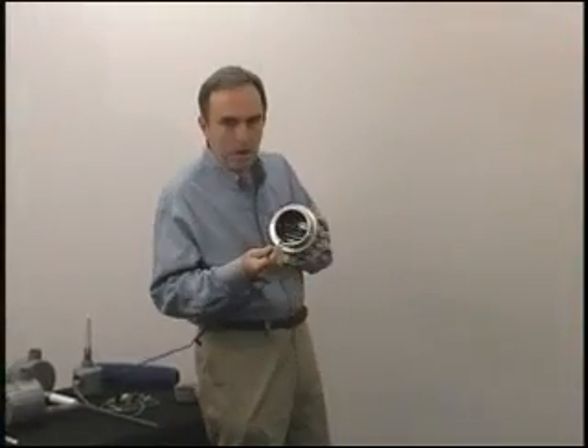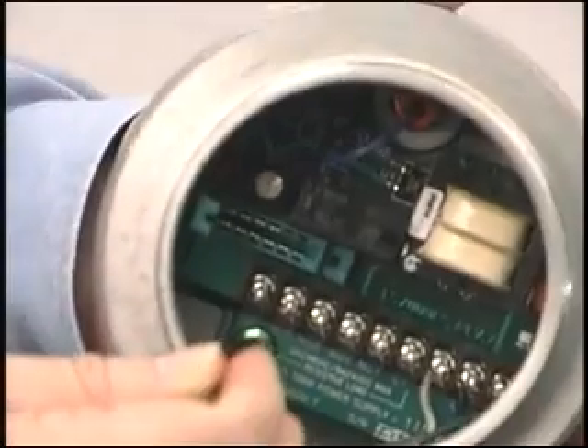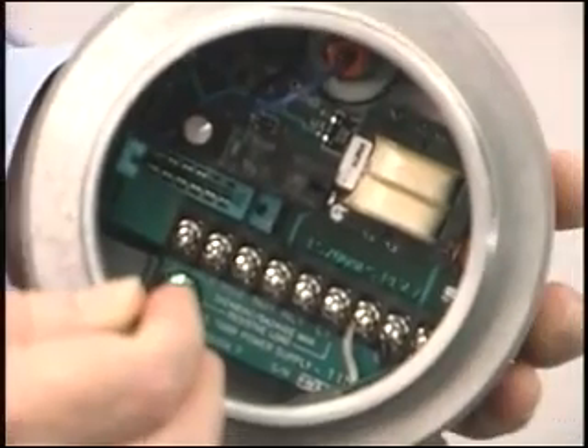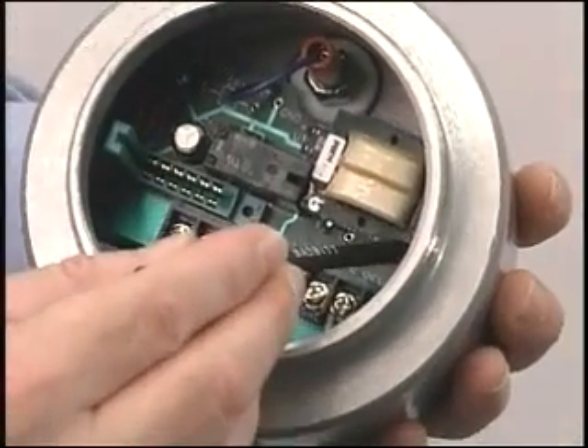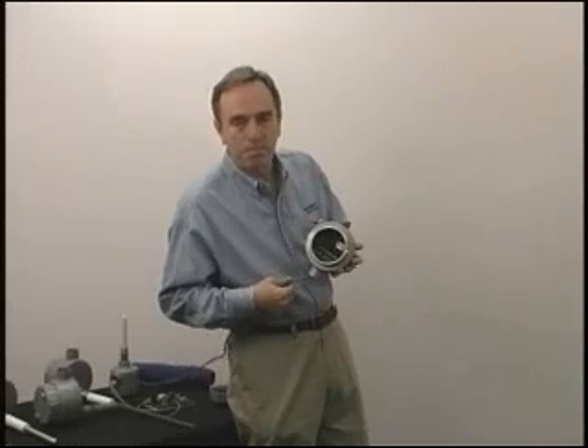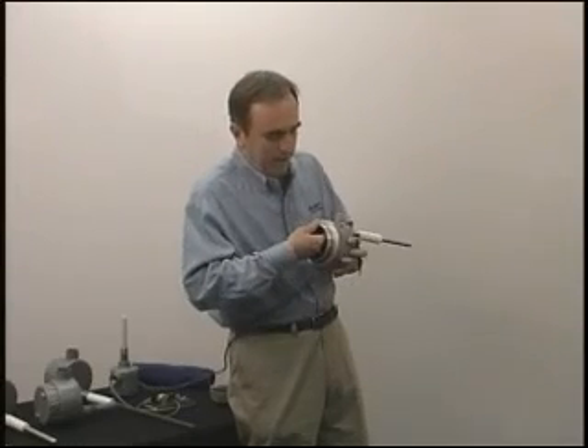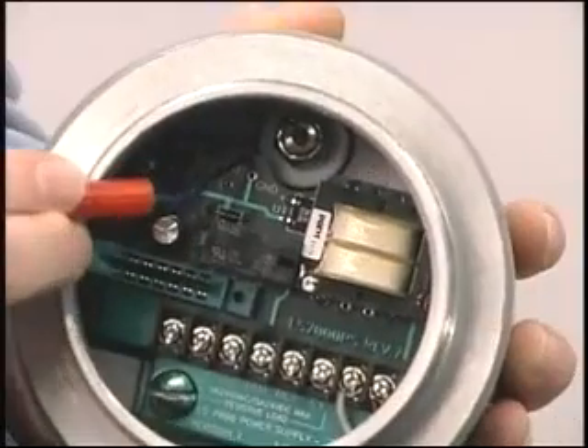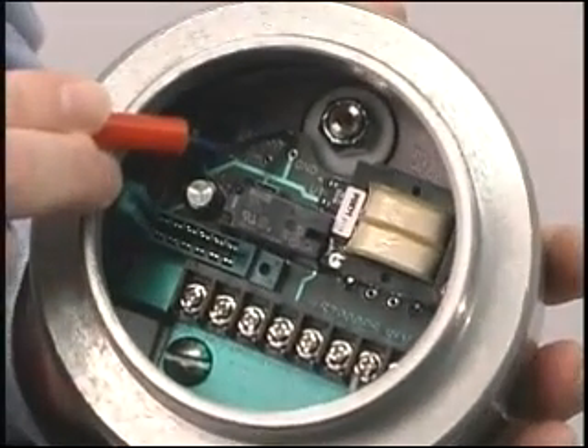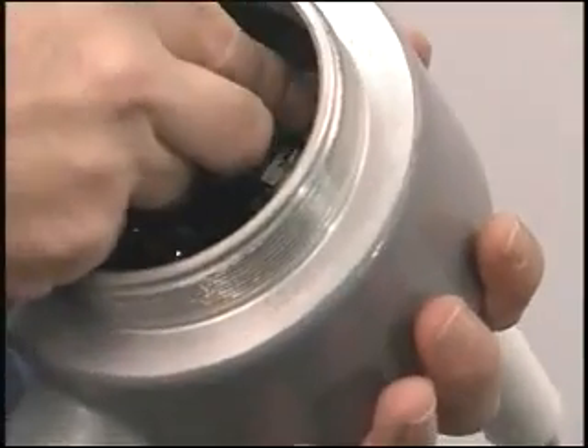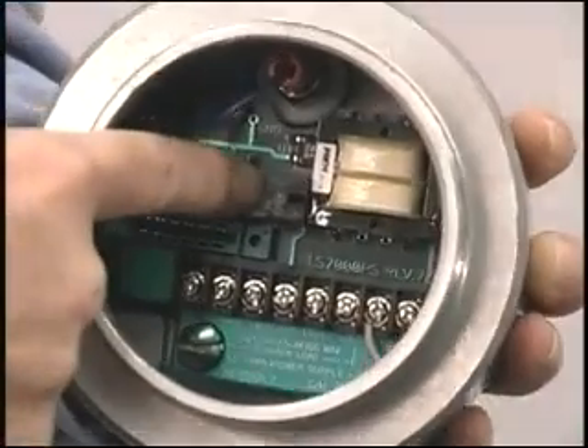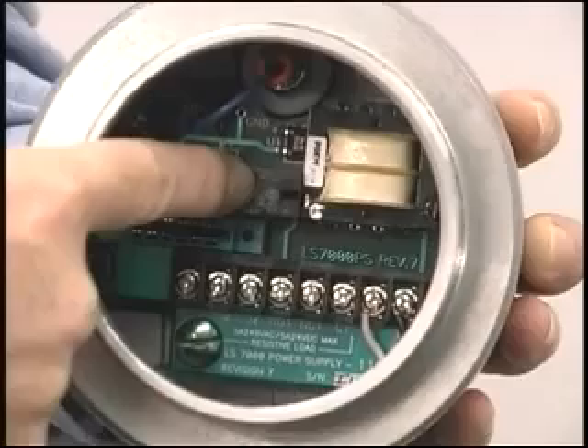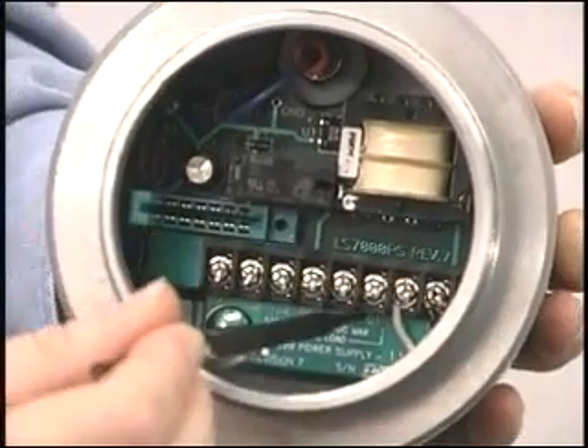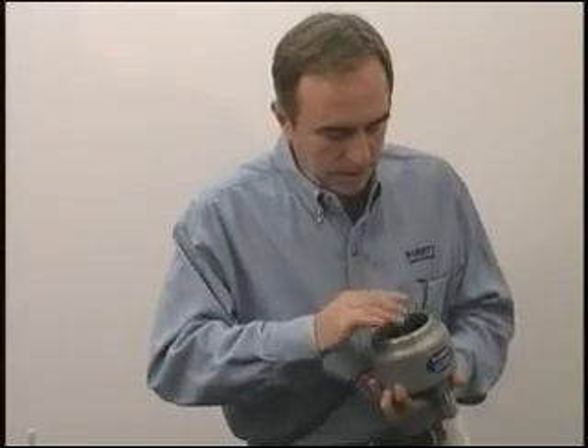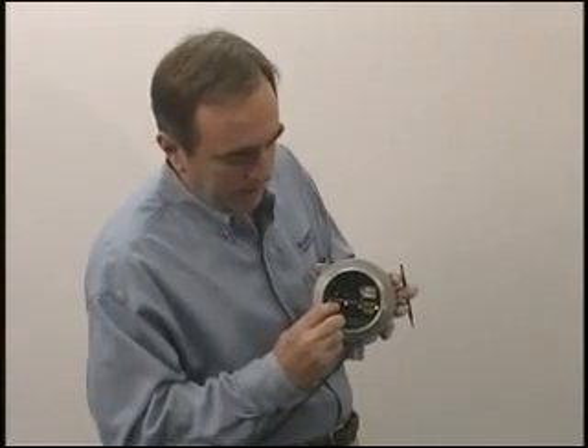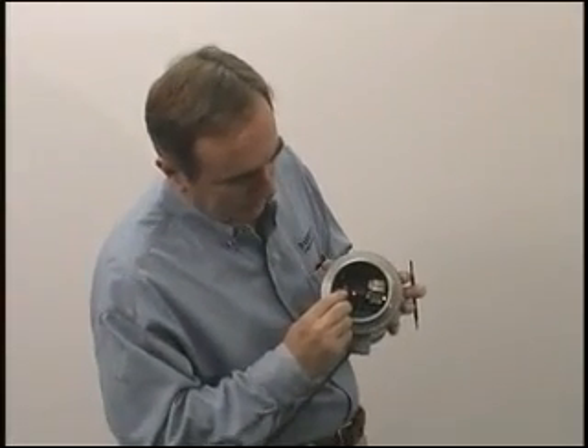The bottom card is what we call the power supply board. There's a large green grounding screw here that holds the electronics in place. There's a built-in fuse and surge arrestor that protect it from bad supply voltages. And that solid stainless steel rod just has a hole drilled in the end. The banana plug loads the signal onto the probe. So very quick change out in the field. The relay output is 5 amp double pole double throw. Bring your power in over here. Your relay contacts out here. Plug in the electronics. There's that test switch I was telling you about.